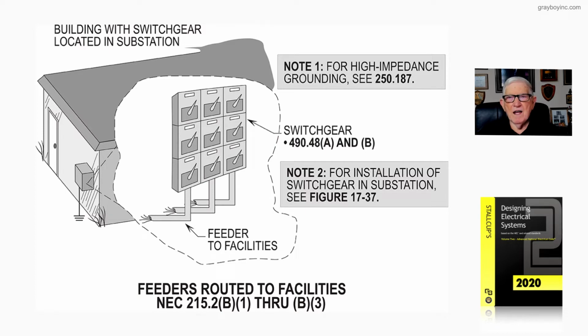Now, for high impedance grounding, you need to make that installation coordinate to 250.187 for over 1,000 volts. And basically, when you high impedance ground, you can fix the system and design it so any ungrounded leg could go to ground and it wouldn't open up the overcurrent protection device of that particular feeder in this case.